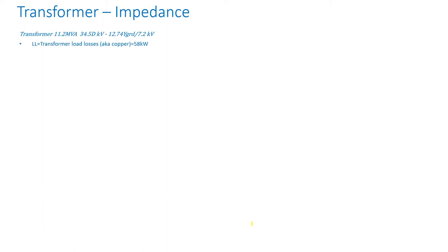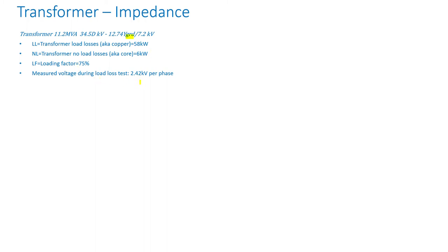Now let's do some calculations with impedance. Consider a transformer rated 11.2 MVA, 34.5 kV delta and 12.74 kV Y-GRD, where GRD means the Y has a grounded neutral. The load losses are 58 kilowatts, core losses are 6 kilowatts, and the loading factor is 75 percent. The measured voltage during the load loss test is 2.42 kV per phase. During the load loss test, rated current is circulated on the high side while the low side windings are shorted. The voltage required to circulate rated current is called the impedance voltage.